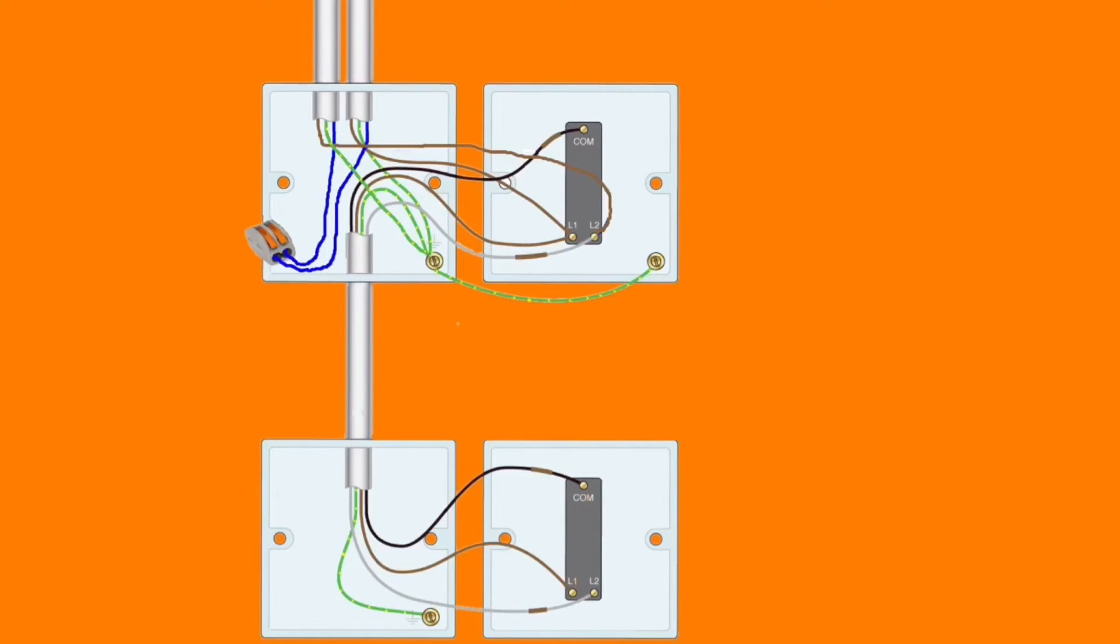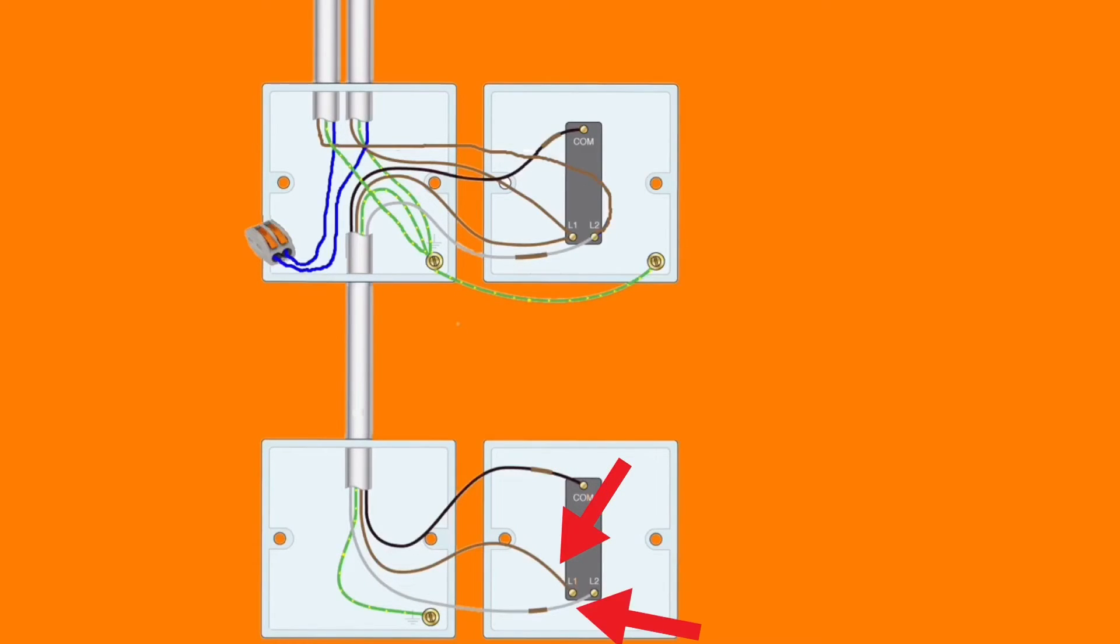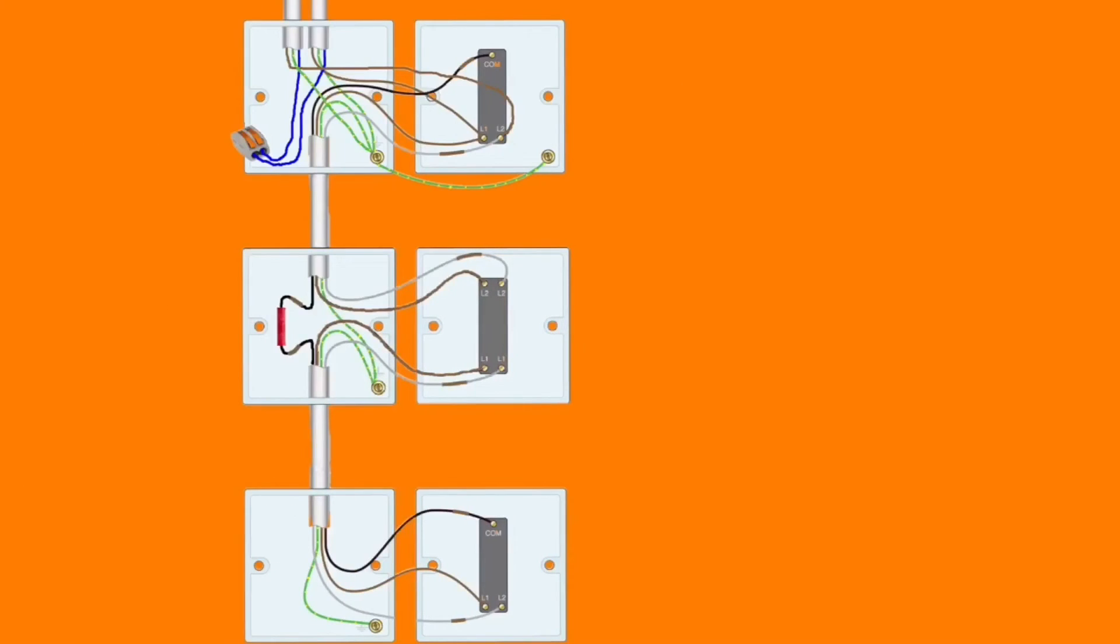So we've introduced the three core from the top switch to our new switching position. Both switches are now two-way switches and our connections in our bottom switch are black for common identified with brown sleeving, and it doesn't matter which way around we have our brown conductor and our grey identified with brown sleeving into L1 and L2. So now we've achieved two-way switching of our lighting circuit. So now we've got two-way and intermediate switching.